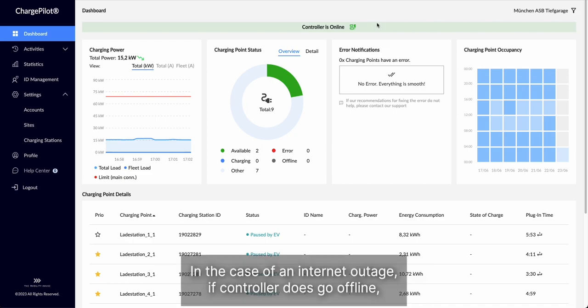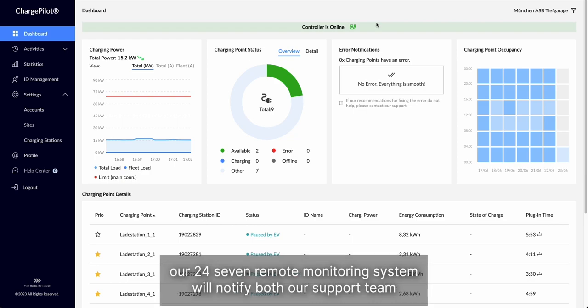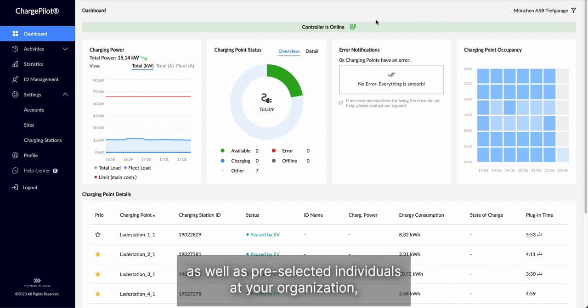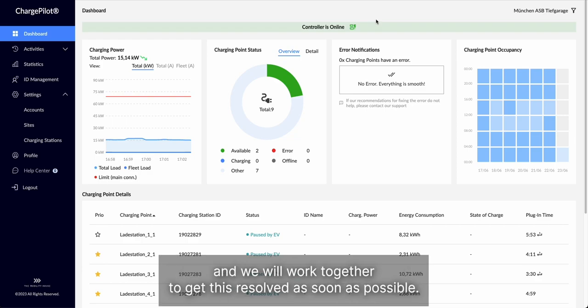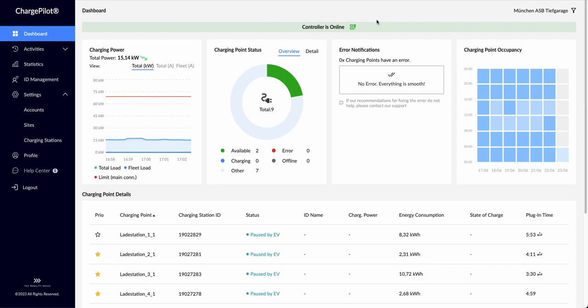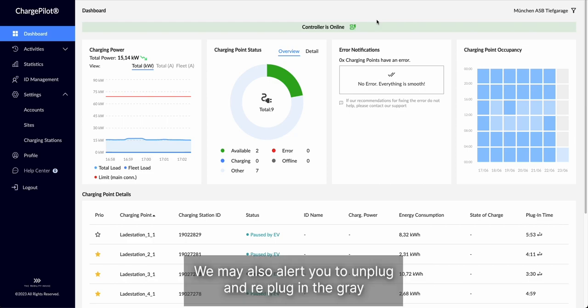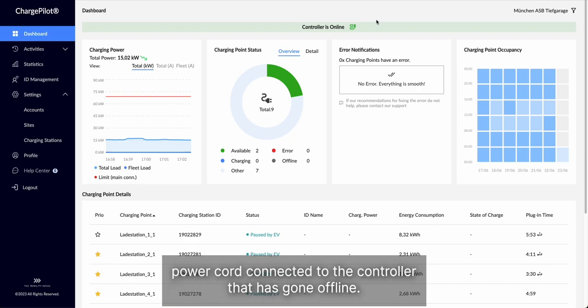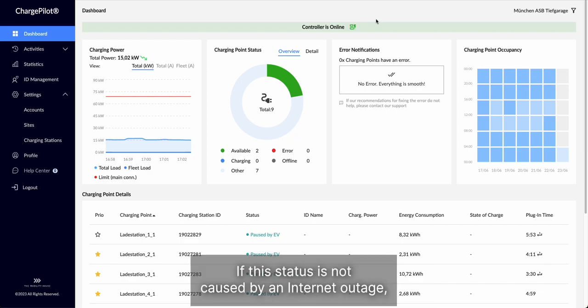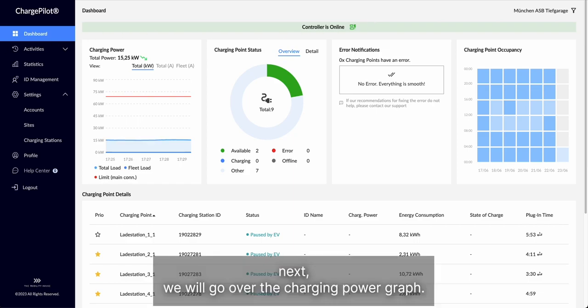If the controller does go offline, our 24-7 remote monitoring system will notify both our support team as well as pre-selected individuals at your organization and we will work together to get this resolved as soon as possible. We may also alert you to unplug and re-plug in the gray power cord connected to the controller that has gone offline if this status is not caused by an internet outage.